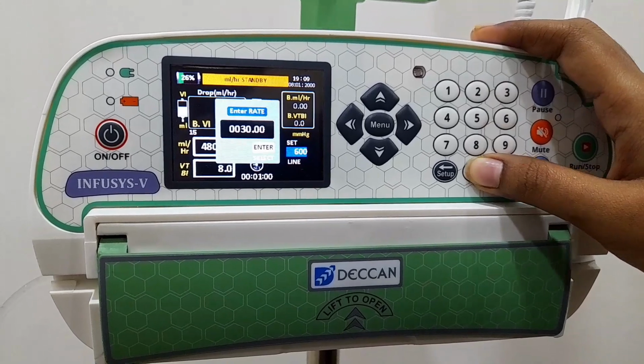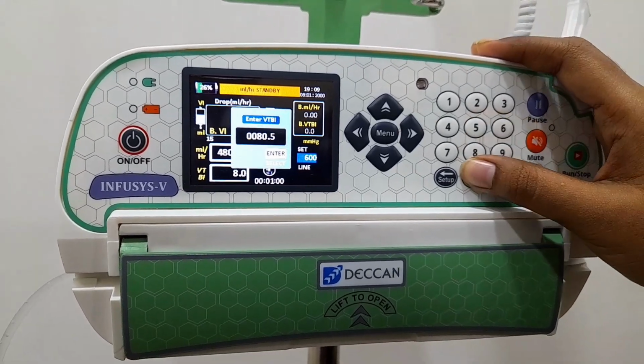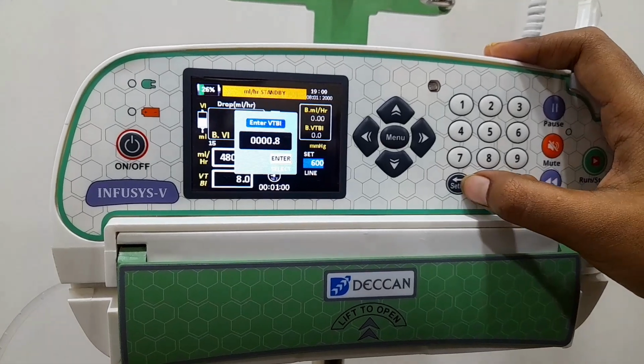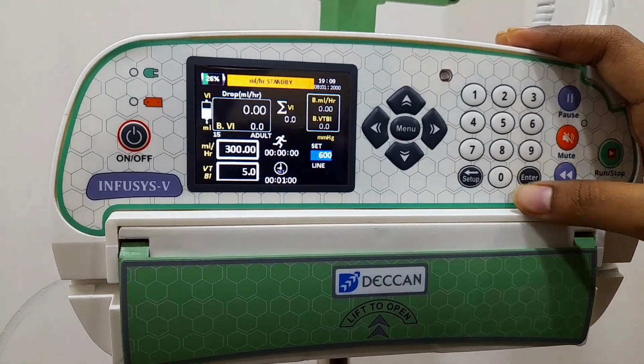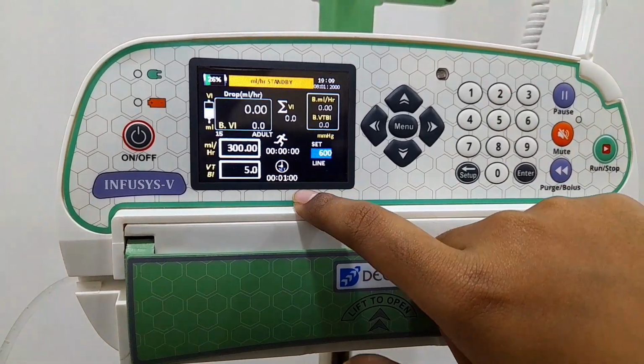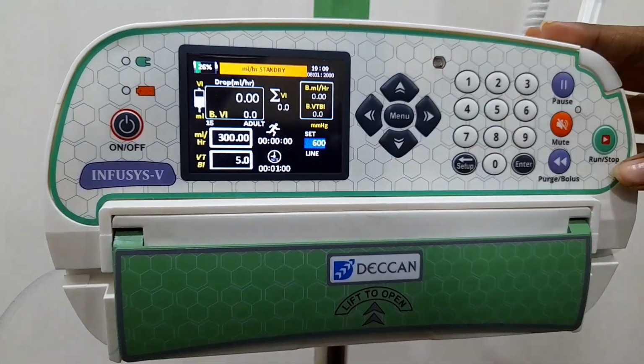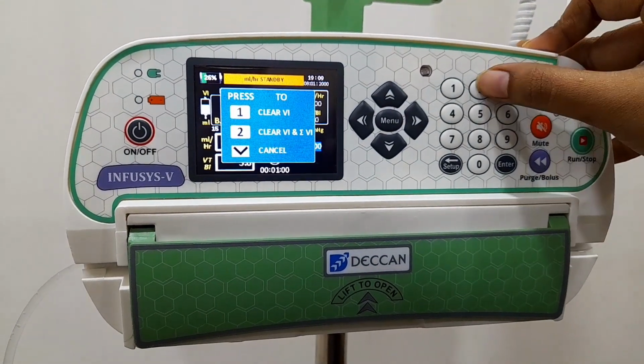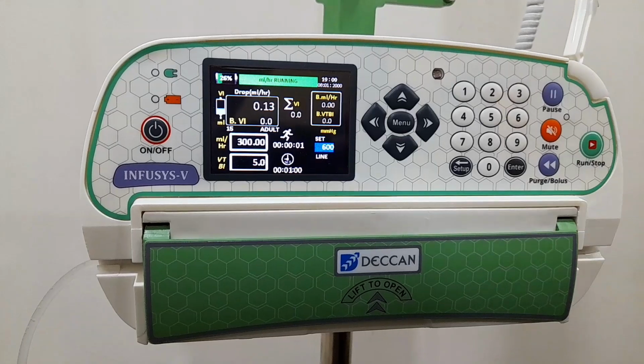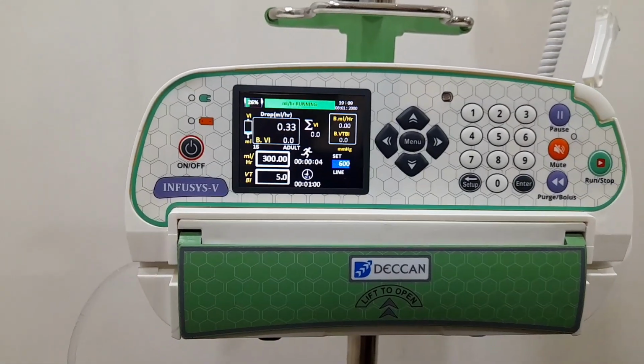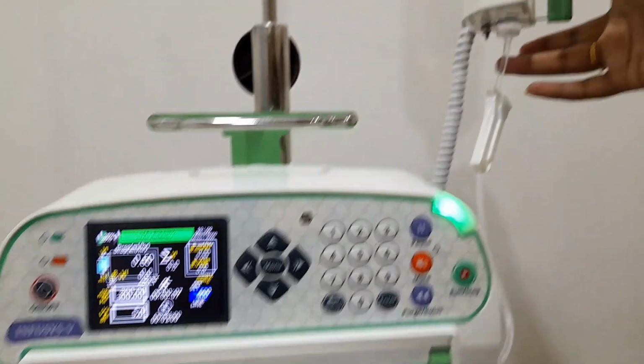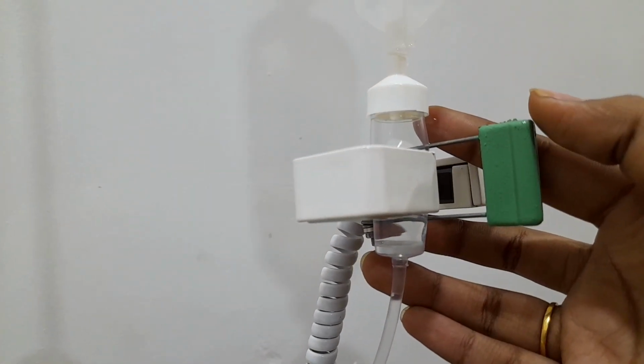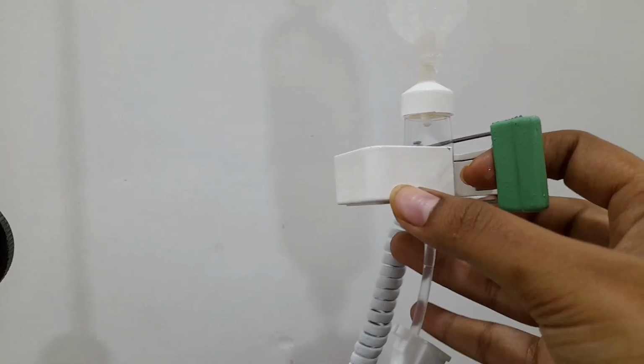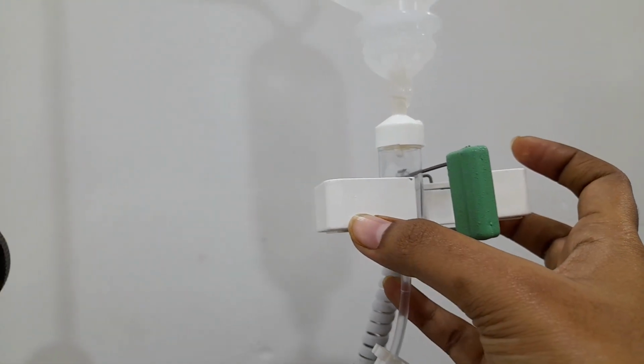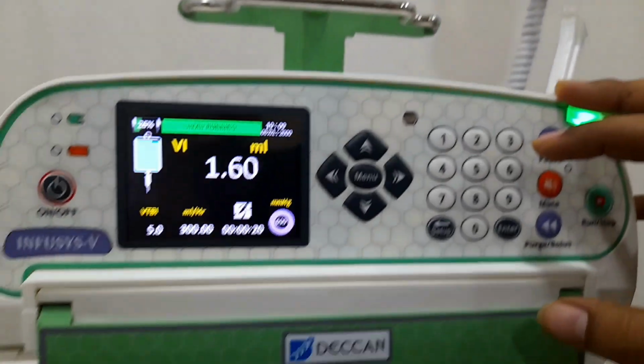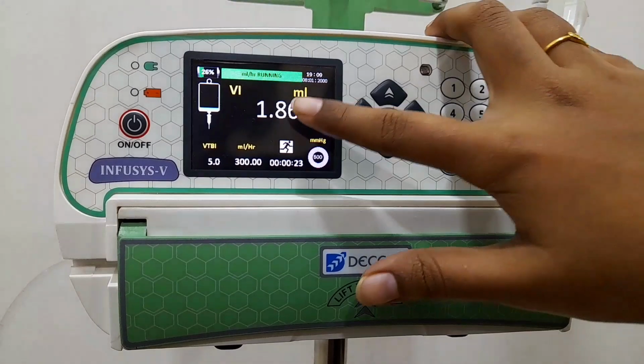Before that, we have to set the rate and VTBI. Here we can set the rate as 300 ml per hour and VTBI as 5 ml. Based on this, the calculated time is 1 minute. Now we can start the infusion using the run/stop key. Press 2 to start a new infusion. Once we start the infusion, the ml per hour running status is updated in the status bar because it is drops based on ml per hour. As said before, based on the drop sensor module and progress bar, we can see the changes in the volume infused.